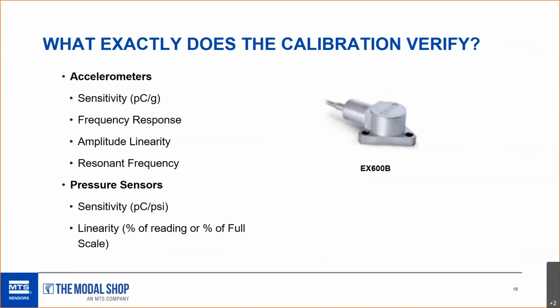Another one that we do at the original factory calibration quite often is insulation resistance. That can be a valuable indicator of the sensor health, or its future health if the sensor insulation drops. That's usually an indicator that the hermeticity is lost, right, Mike? Yeah, these sensing elements in here need to be sealed from any kind of weather conditions, moisture, any kind of toxic materials, and they need to be kept dry and clean. And we do that with a hermetic seal around all the connectors and the sensing element.